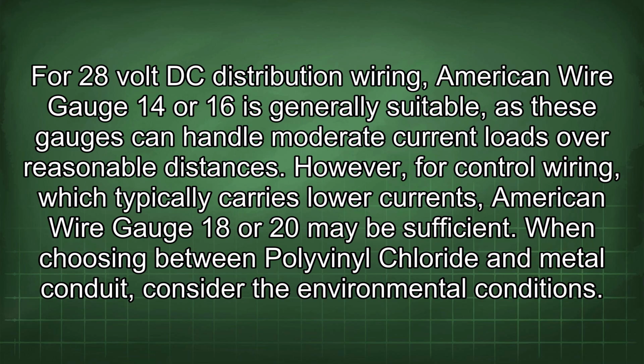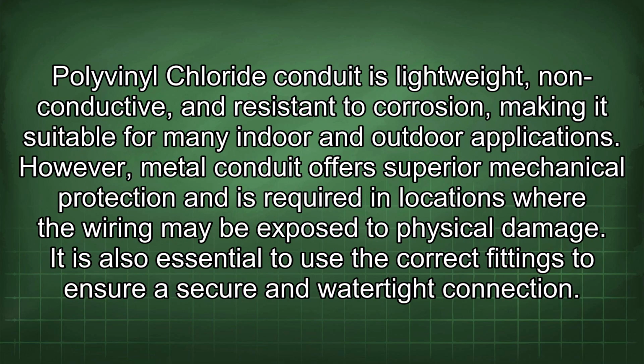When choosing between polyvinyl chloride and metal conduit, consider the environmental conditions. Polyvinyl chloride conduit is lightweight, non-conductive, and resistant to corrosion, making it suitable for many indoor and outdoor applications. However, metal conduit offers superior mechanical protection and is required in locations where the wiring may be exposed to physical damage. It is also essential to use the correct fittings to ensure a secure and watertight connection.